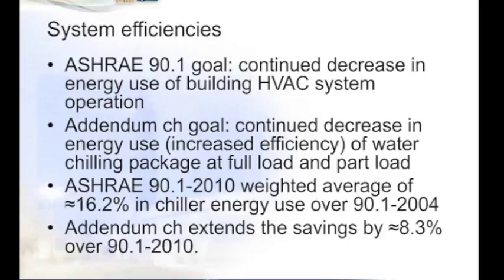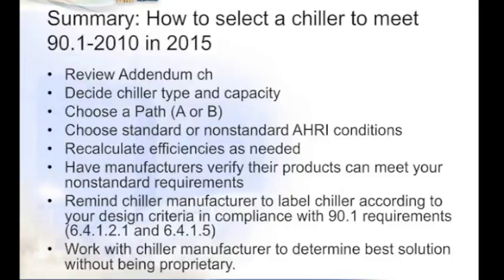So to begin the summary: how do you select a chiller to meet these conditions in 2015? Obviously, it's important to know as much as you can about the codes and standards by reviewing this addendum in particular. You need to decide on what your project requirements are and what type of chiller can best suit the needs, whether it's air-cooled, water-cooled, or anything in between. You need to choose the path and the values that best suit the planned operation. You need to select the design conditions and recalculate efficiencies if needed, either to match your goals or to have the equipment selected correctly.